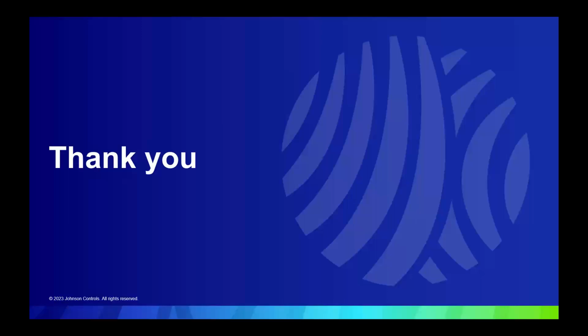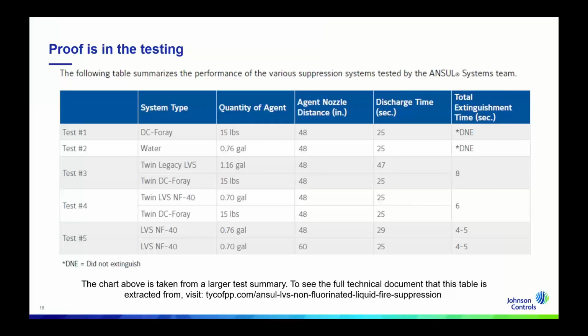The only question we have so far is regarding the measurement between the nozzle and the hazard area, asking whether that is the measurement referred to, or if it was actually a pipe length or hose length. So the question is, for the LVS testing, is that agent nozzle distance the distance from the nozzle to the hazard, or the pipe length from the tank to the nozzle? The answer is it's the distance measured from the tip of the nozzle to the fire hazard. Thank you.